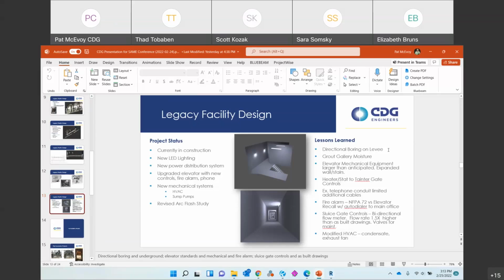Another lesson learned was in the grout gallery, there's a lot of moisture. The fixtures we picked were not necessarily wet location rated, but they are NEMA 4X design, though that may not be exactly right for wet locations. We've got aluminum housing, so we're hoping it'll last, but the fixtures we picked may not be the best for that environment.